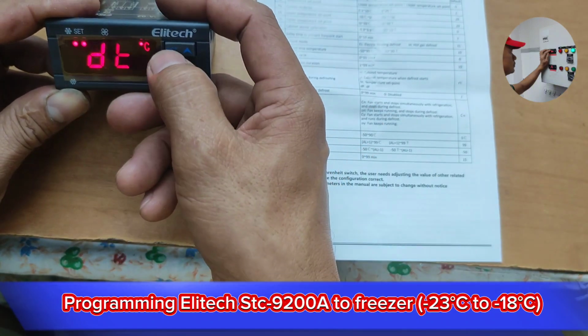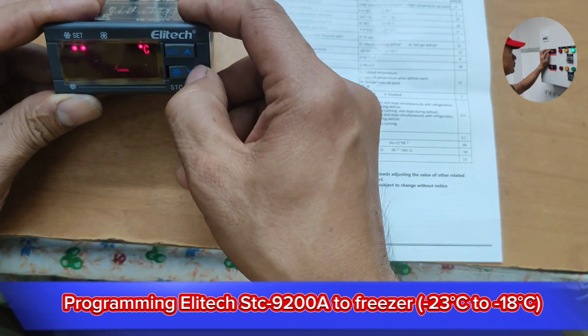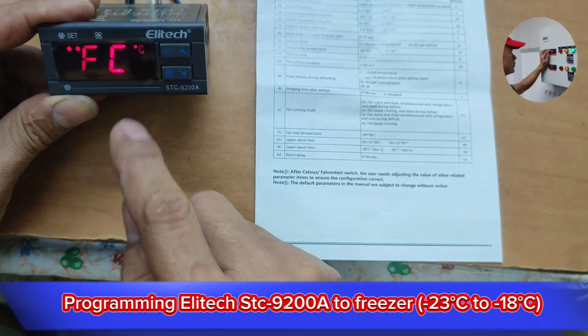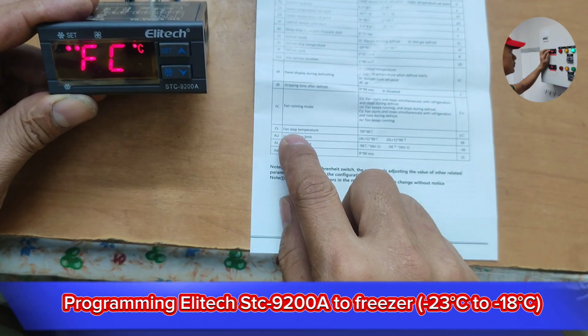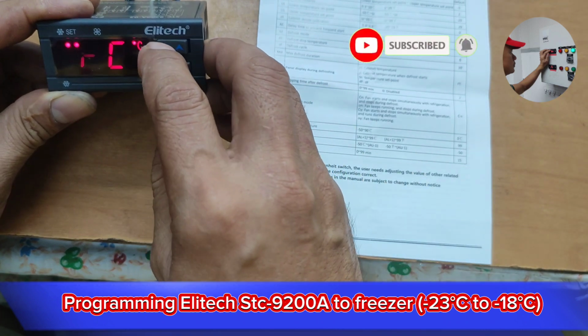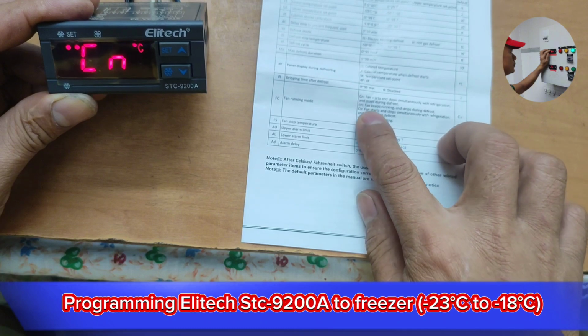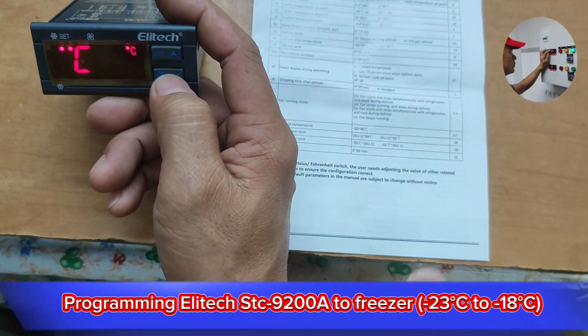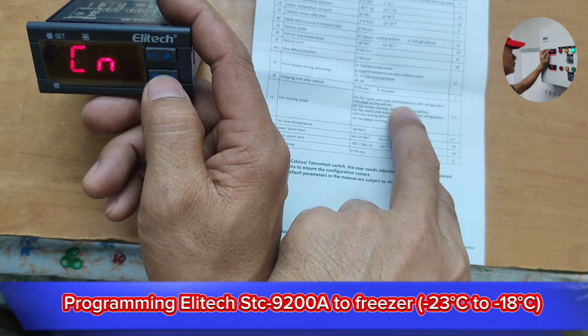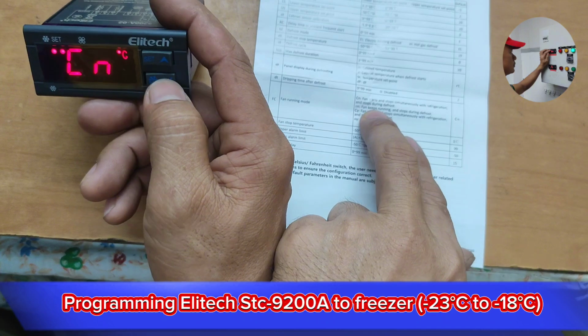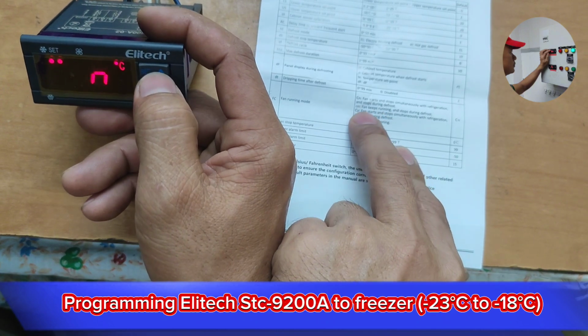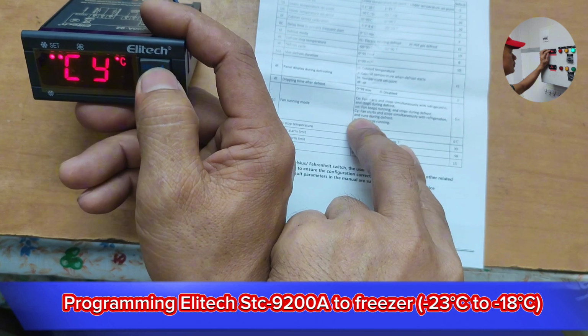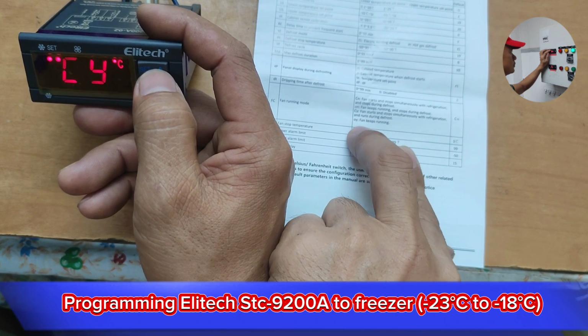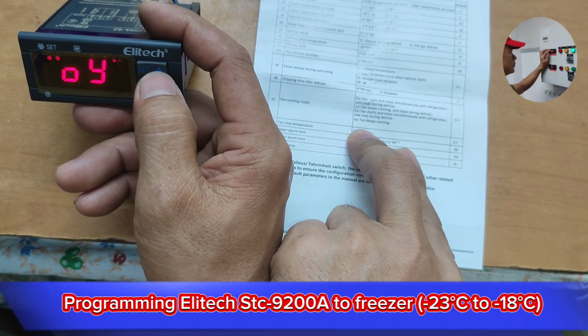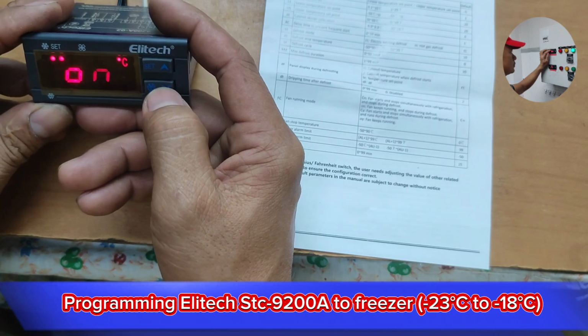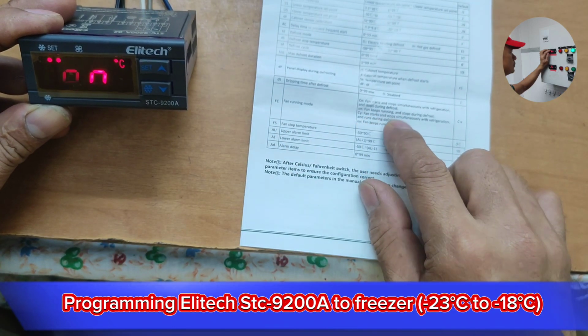And DT, dripping time after defrost, we're going to set that to 2 minutes. If you want 3, you can go with 3. Temperature set, 3 minutes. FC, fan running mode, press set. We're going to select CN. CN stands for fan starts and stops simultaneously with refrigeration and stops during defrost. ON, fan keeps running and stops during defrost. CY, fan starts and stops simultaneously with refrigeration. OY, fan keeps running 24/7, that's not ideal. So we're going to select ON here: fan keeps running and stops during defrost.